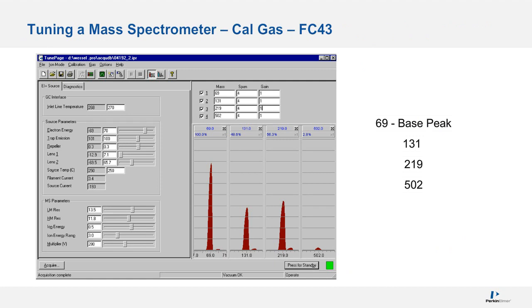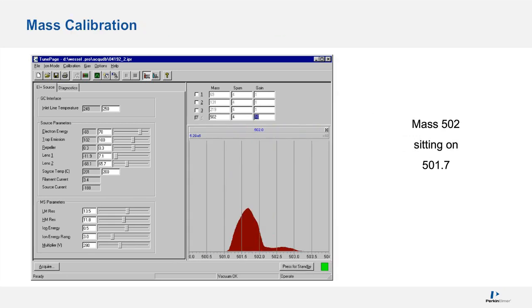This is typically what we tune to, these four. Remember, you have to meet tuning criteria, but tuning is really an art. What's not an art is mass calibration. If the mass is off a little, it isn't that bad, but if you see your mass floating, that's when you have to mass calibrate. Mass calibration is a science. I mean, the mass is its mass.